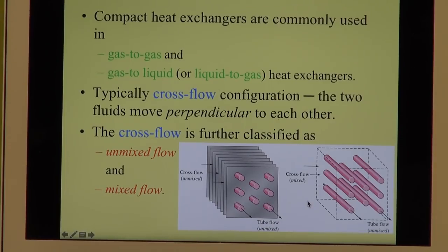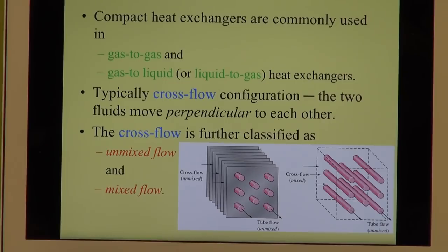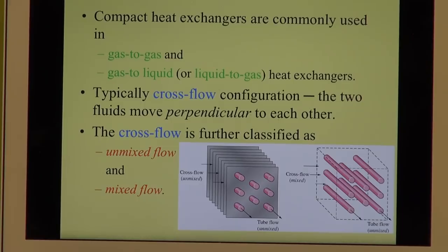In most cases where heat transfer involves air — which is very common in mechanical engineering — air has a very small heat transfer coefficient. That is the reason why we use fins. Fins on the outside are typically seen in condensers and evaporators in the HVAC industry. The gas or air can be in natural convection or forced convection where we normally use a fan.